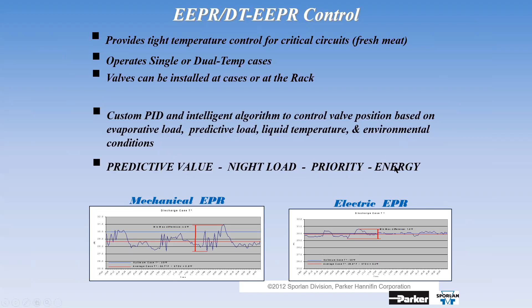So here's what we started to pack into there. Whether it was a CDS 4, 7, 9, 16, or 17, we didn't go with the catalog value of the valve. We actually tested each and every valve, and we shaped the control of that based on the actual output of the EPR, which meant we weren't controlling to a theoretical capacity. We are controlling to an actual flow capacity. Again, that enables you to get your money's worth. You're paying for electronic control.